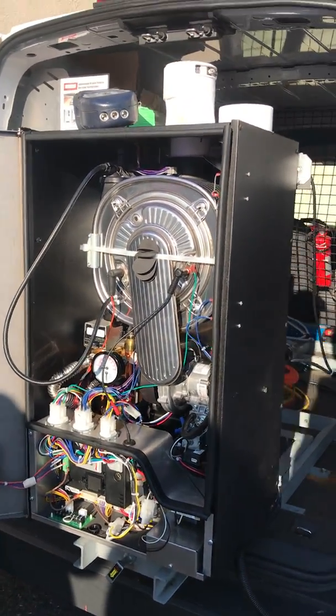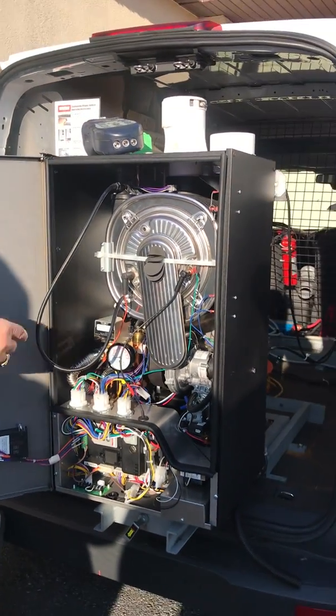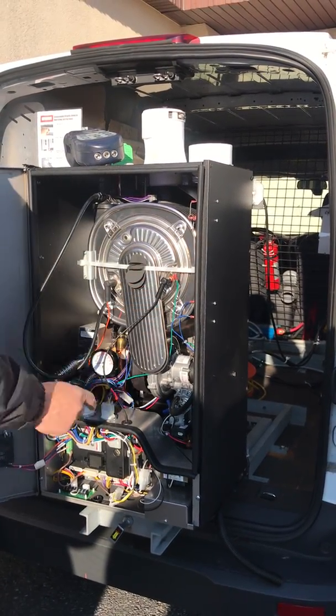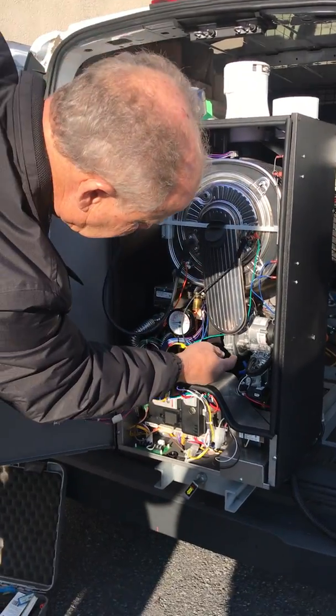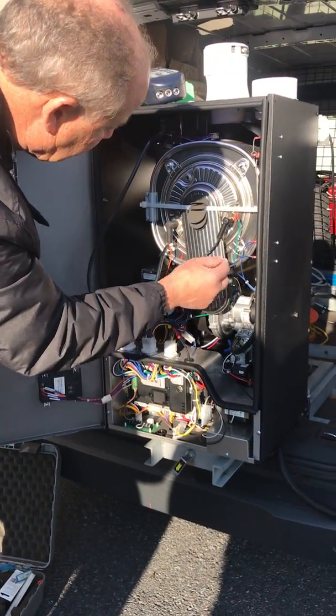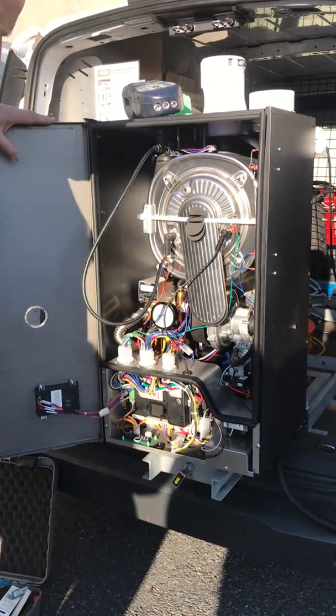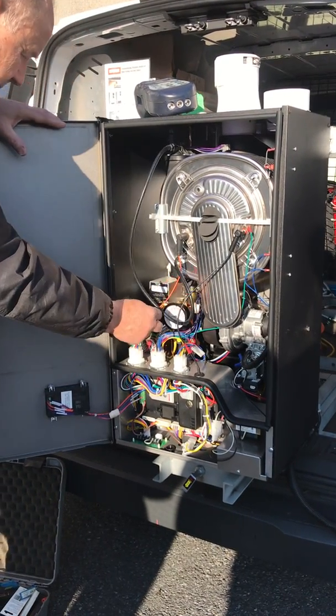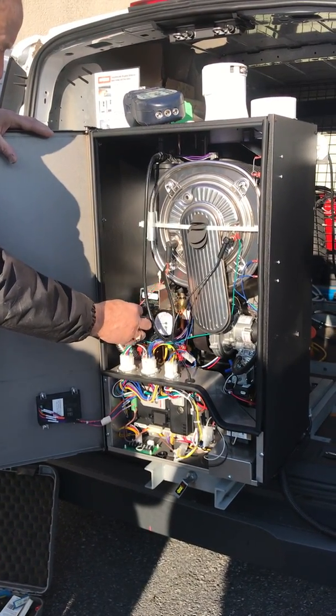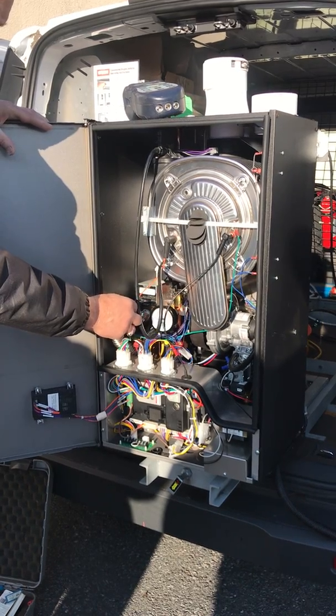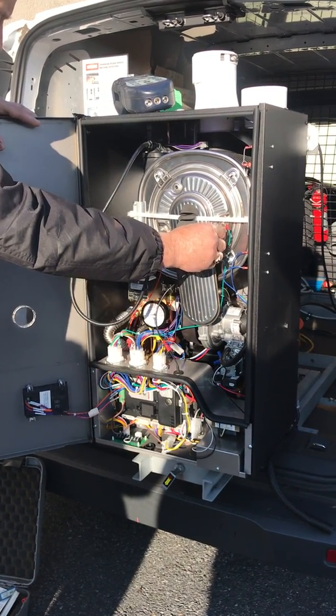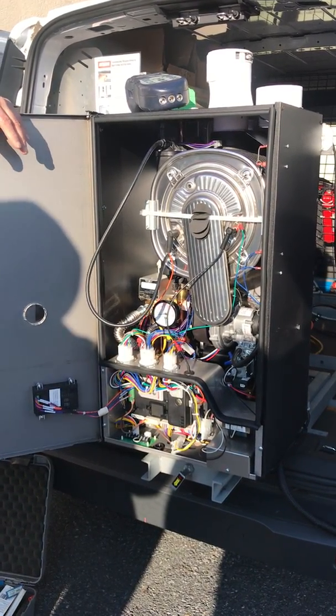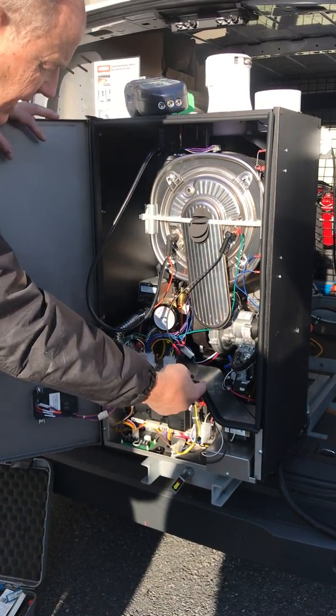To convert this from natural to propane, I take these 4 nuts off. I can basically pull my wires off of this. There's a signal wire that actually measures the flame signal, and there's a spark cable. So I can pull those wires off. And then I disconnect my gas.